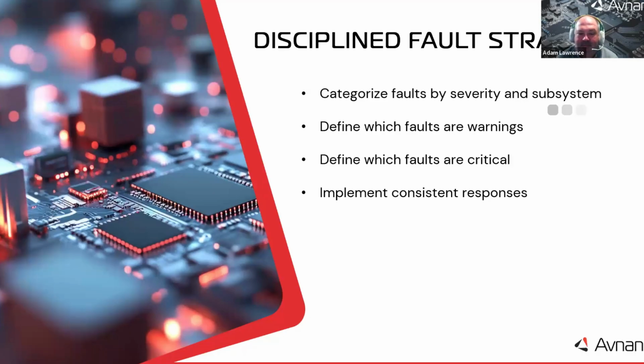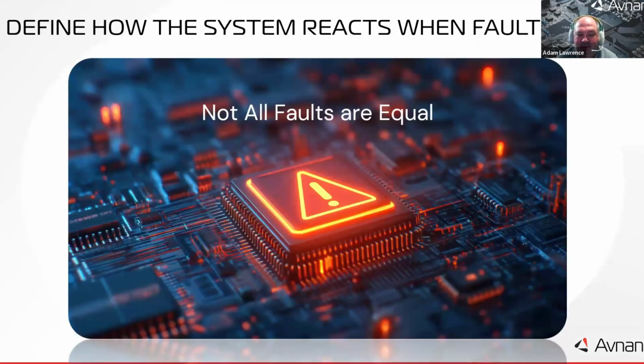Beyond naming, a disciplined fault strategy includes categorizing faults by severity and subsystem. For instance, you define which faults are warnings, such as a dirty filter, and which are critical, such as a compressor overheating. By doing so uniformly, you can also implement consistent responses. One area where that consistency pays off is how the system reacts when faults occur. Not all faults are equal. Some allow the system to keep running in a limited way, while others require an immediate shutdown to protect equipment or safety.